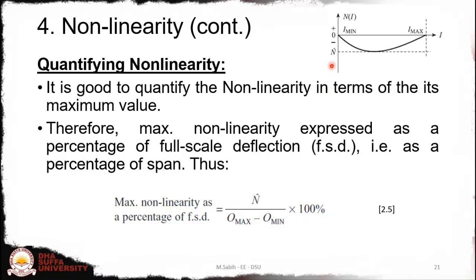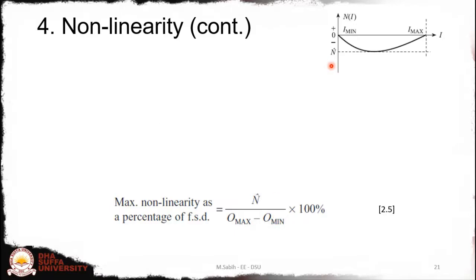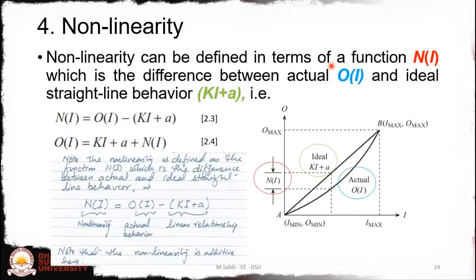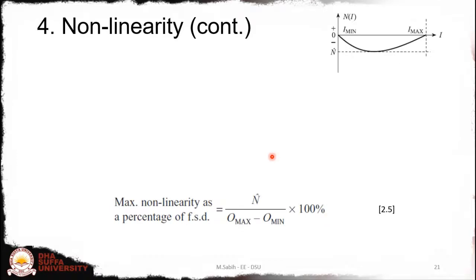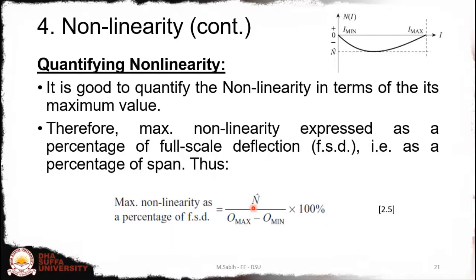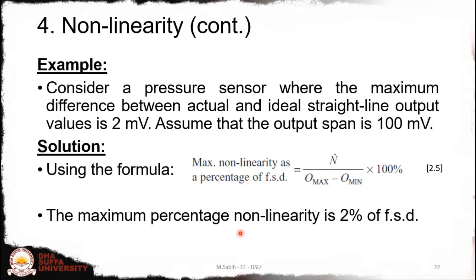Since nonlinearity is basically an output quantity, it appears on the output axis rather than the x-axis. To calculate the maximum percentage nonlinearity, we divide n-hat by the full-scale deflection — that is, the span of the output. This maximum will be divided by the output span to give the maximum nonlinearity as a percentage.